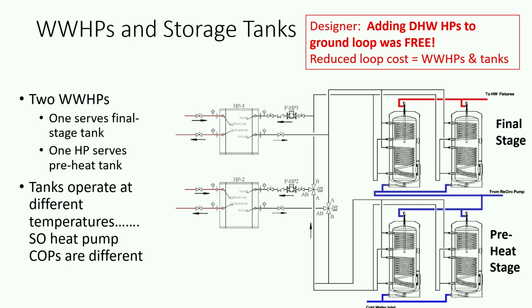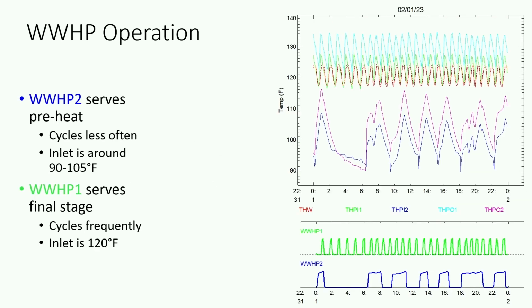And so one of these heat pumps could be used on this set of tanks, and one of the heat pumps could be used on that set of tanks, and they could be swapped. And that's why you see the valves and the plumbing. And the tanks operate at different temperatures, so the COPs are different. So the water-to-water heat pump system, how did it operate?